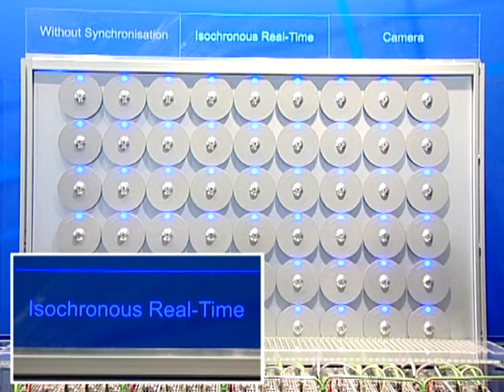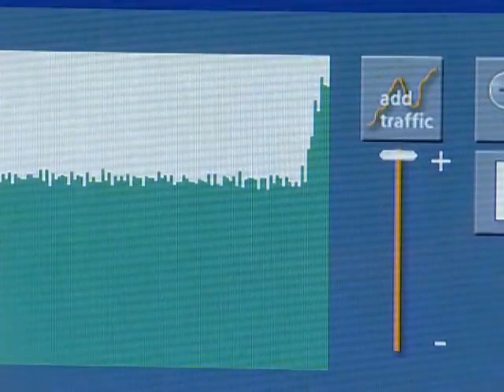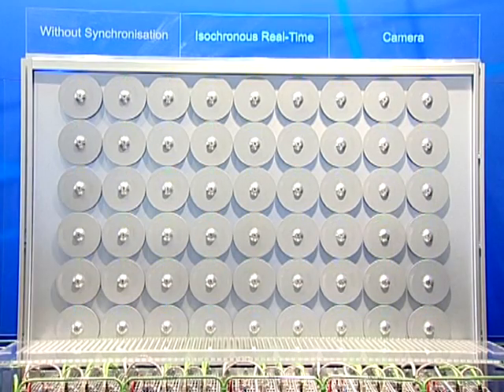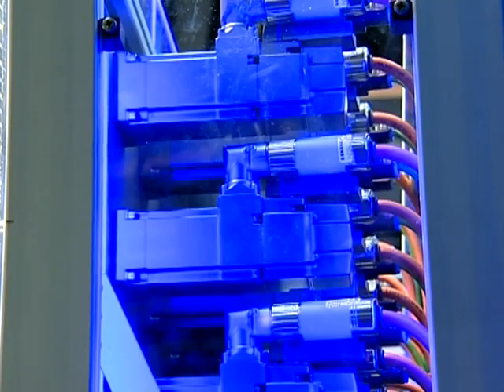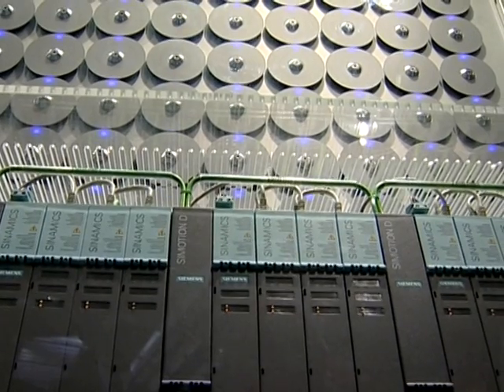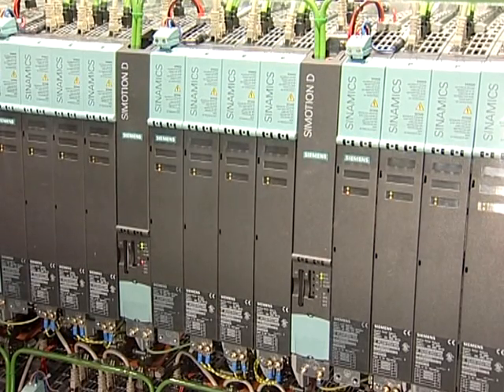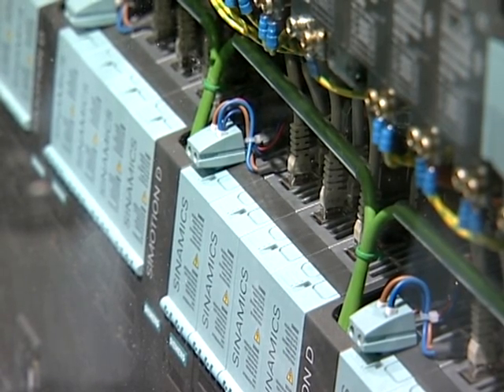Synchronization is re-established by switching in the Isochronous Real-Time mechanism. PROFINET with Isochronous Real-Time guarantees deterministic real-time communications and guarantees that the tough requirements of motion control applications are fulfilled. This continues to function even if the network utilization is increased to the maximum value using additional TCP telegrams. Using PROFINET, you can implement faster machines with higher performance. High numbers of axes and larger data quantities at the lowest cycle times can be taken for granted. Large data quantities, such as cams, can be cyclically transmitted using the IT capability of PROFINET to reduce cycle times and increase productivity.